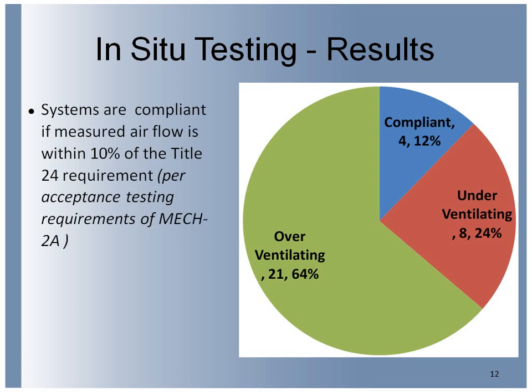And shuffling those data a little bit different, what we find in terms of the across the testing, that 64% of our tests we found the systems to be overventilating outside the prescriptive plus or minus 10 that the Title 24 acceptance forms would dictate as the ventilation compliance range. A few of the systems, about a quarter of systems actually underventilating, and a few that were actually compliant.